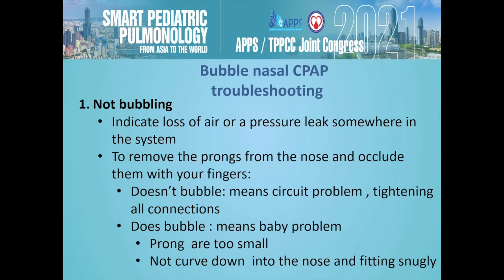How about troubleshooting? When the bubble CPAP does not bubble, it indicates loss of air or a pressure leak somewhere in the system. So remove the prong from the baby and occlude it with your finger. If it doesn't bubble, it means a circuit problem, some hole problem. Tighten all connections as much as possible. If it does bubble, then it means the baby has some problem. Maybe the prong size is too small or not curved down into the nose and fitting snugly. So correct it.